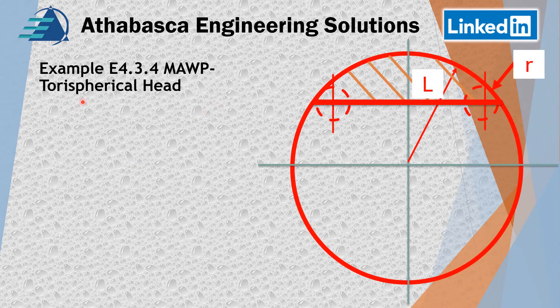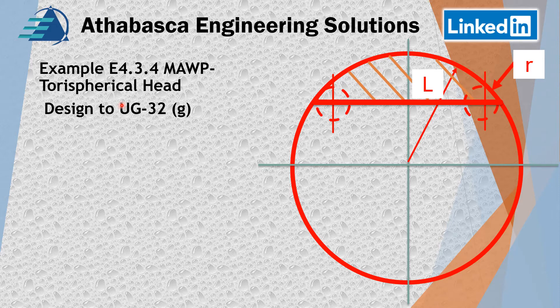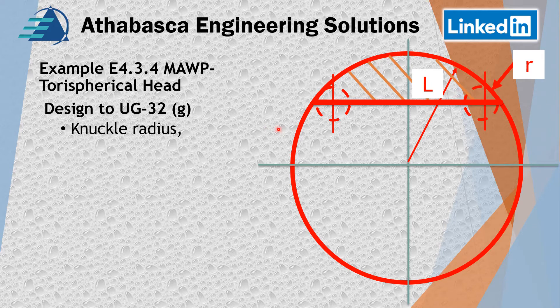Let's discuss a little more about the torispherical head because there's some confusion. ASME PTB-4 allows some latitude on the design, but in most cases I recommend you just follow the PTB-4 definition of the torispherical head. There are comments in UG-32G about the knuckle radius — this part here is what I drew for this torispherical head. Outside there is the shell, and basically you have the small knuckle radius and L, the crown radius.